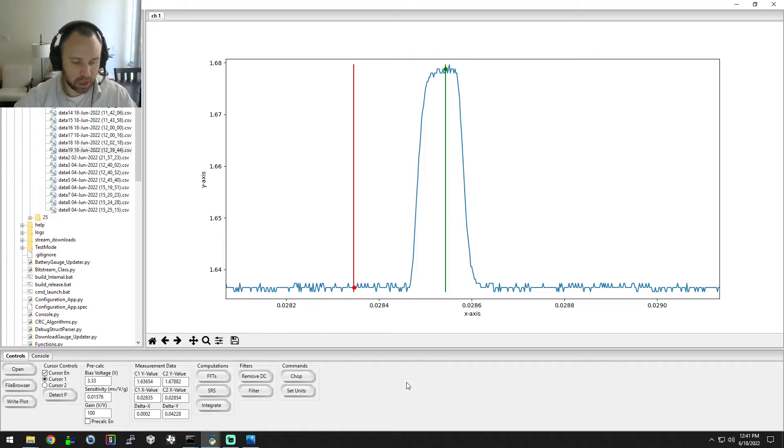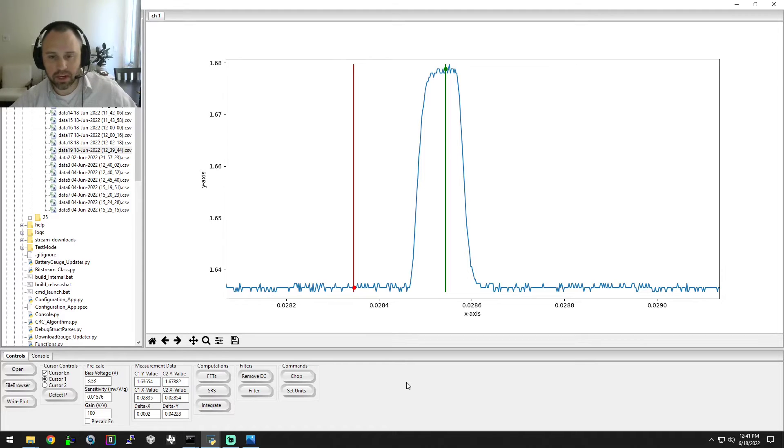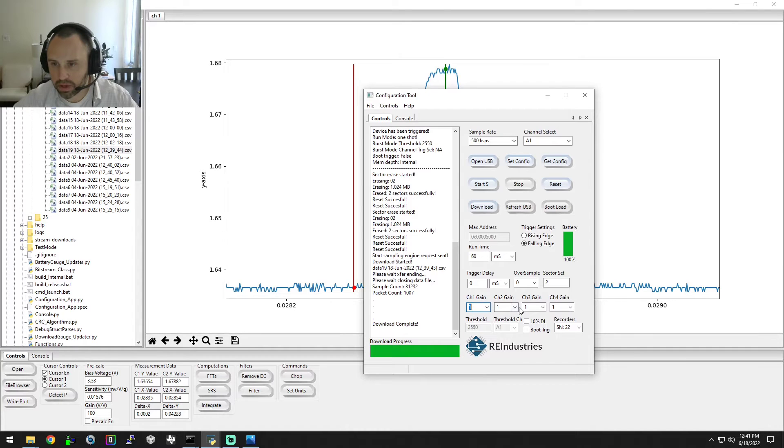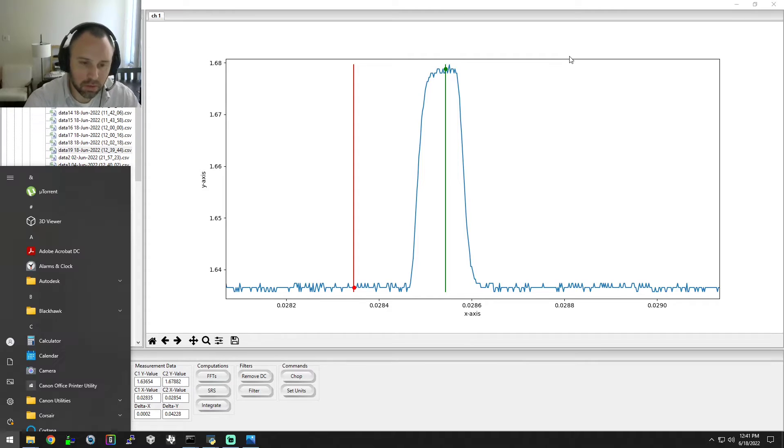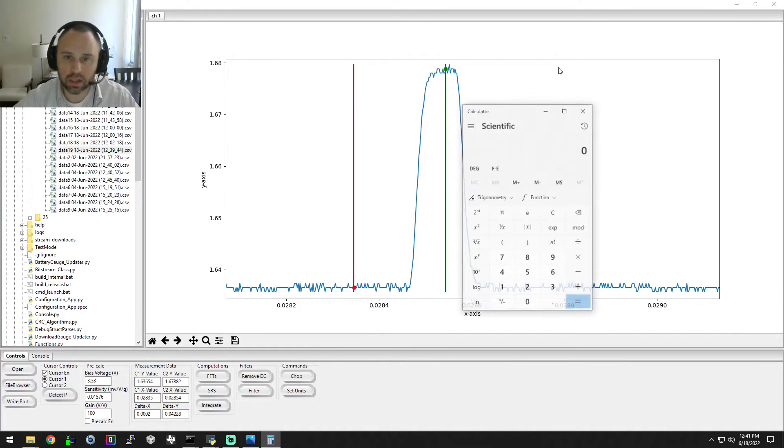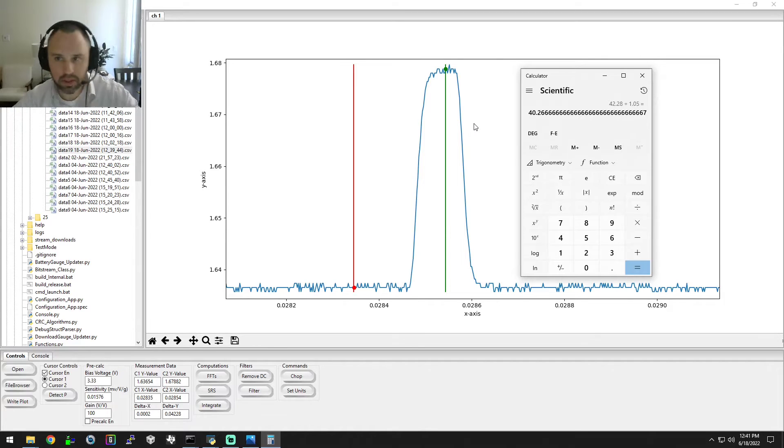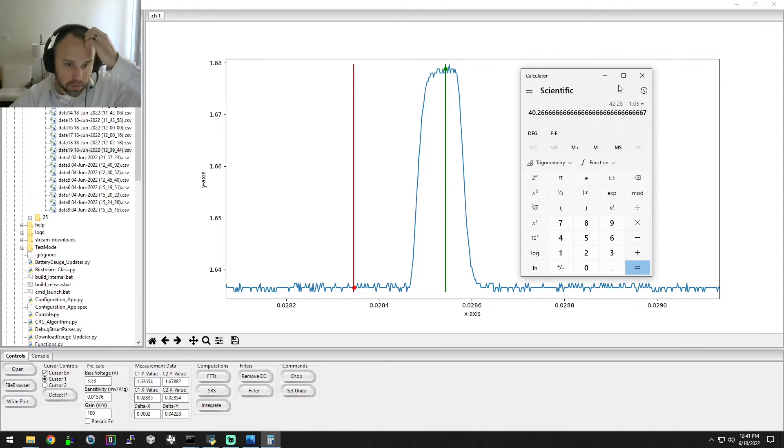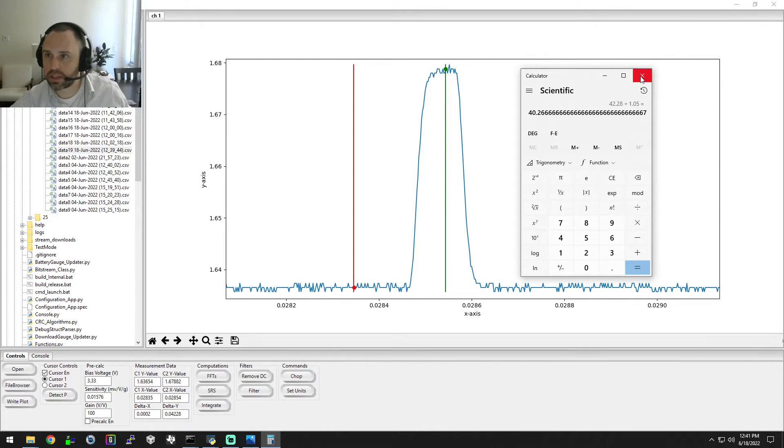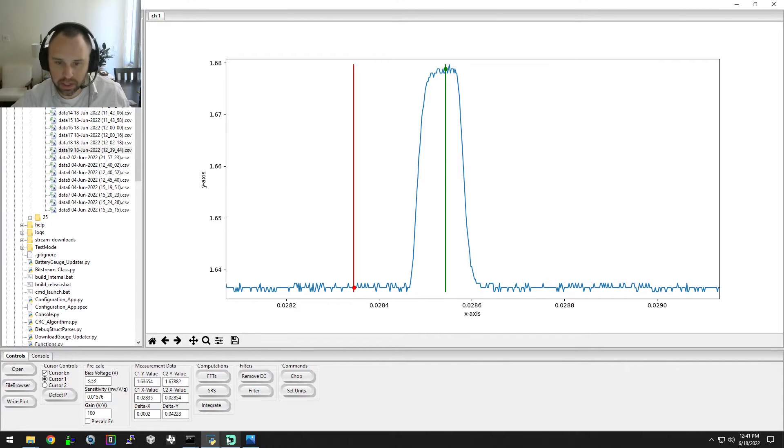One thing to note in this example is that these recorders come calibrated with a calibration value for a gain of one. In the configuration here each channel will have a calibration value for one because it's not exactly one, it's a little bit above 1.0. In this case our cal value during production is 1.05, so if we take the delta 42.28 and divide that by 1.05 we get roughly 40 millivolts, a little bit over, but we're pretty much right on the money with this signal generator and our input stimulus. So this pulse is still quite small but it matches.